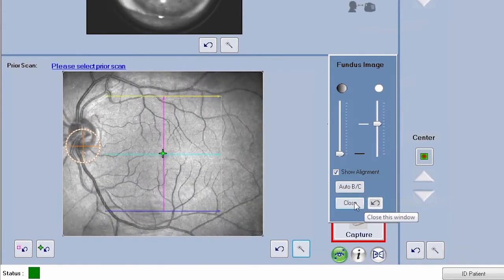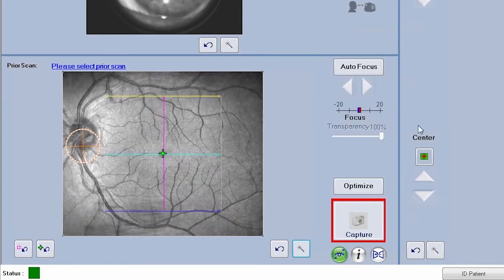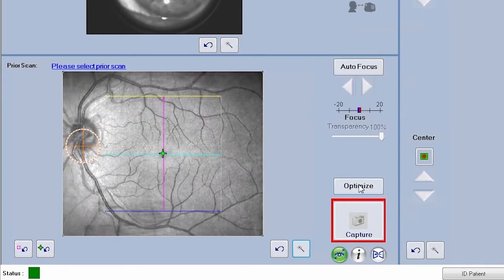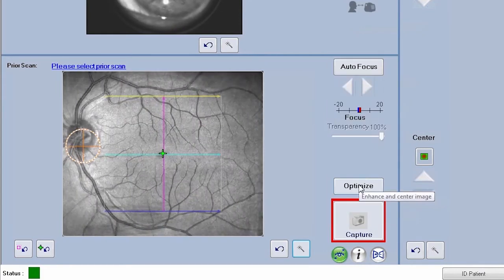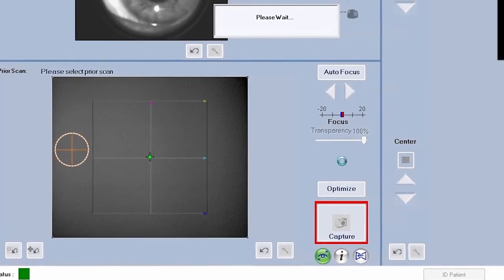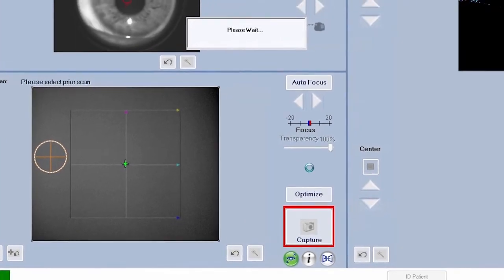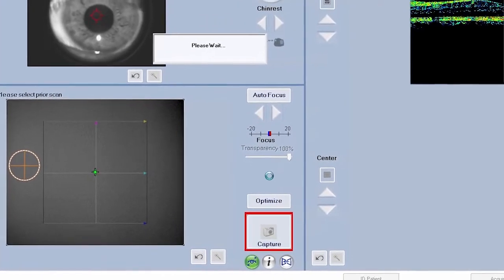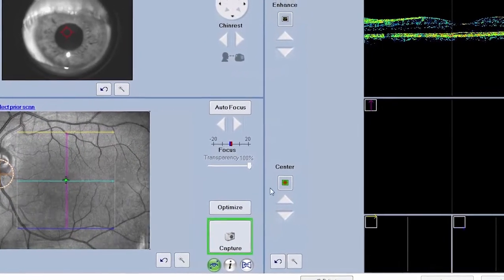After aligning the fundus, focus the OCT image next. For optimal signal strength for the OCT image, click on the optimize button located in the fundus viewport. This will automatically enhance and center the OCT scan patterns.